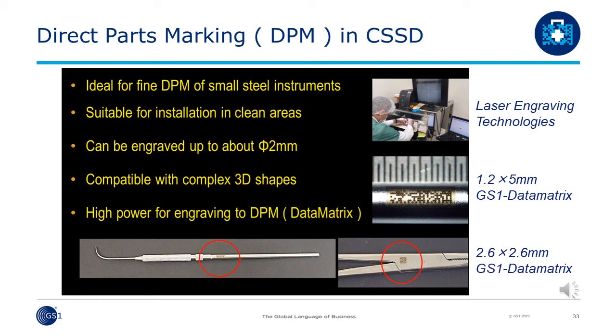This slide introduces direct parts marking, DPM, which is performed inside CSSD. First, we examined the method of marking UDI on surgical instruments. As a result, the following method was tried many times and finally established. Establishment of laser marking method. The engraving method was examined from various laser devices. The engraving depth was 20 microns, which was strong against scratches. As a measure against rust, post-treatment was performed to remove debris.